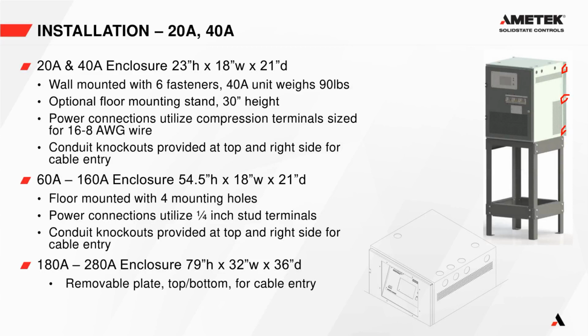The power connections utilize compression terminals, and they can fit between 8 gauge and 16 gauge wire to the input and output. And we have the conduit knockouts that allow for right side or top cable entry.